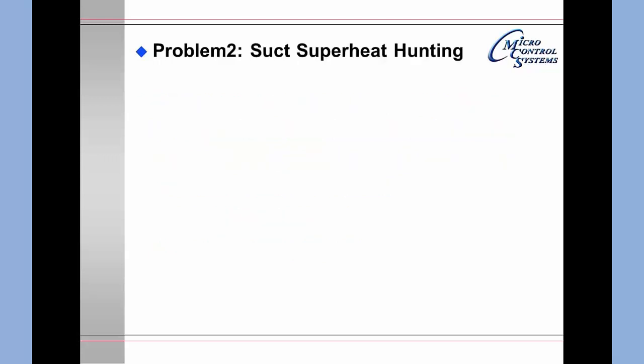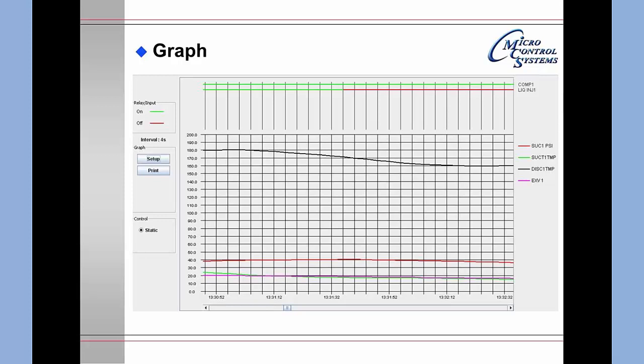The next problem is that our suction superheat was hunting. We have a graph showing the interaction of data that helps us analyze what the problem was. Looking at this graph, you can see that the compressor is on and the liquid injection is on and then the liquid injection goes off. During the time frame that the liquid injection is on you will notice that we are at about 180 degrees.